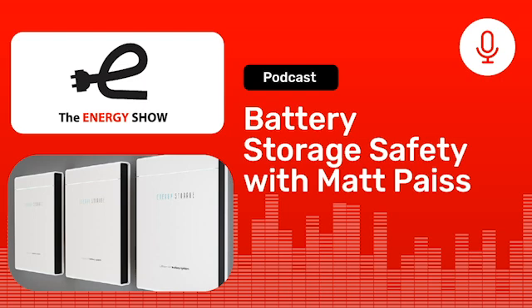The first thing they should look for is to see that it is UL listed, and that listing is 9540. So that's the first thing, to really ensure it is listed. There are some challenges with lesser-known batteries—you want to ensure it's a valid listing, as there are always counterfeit issues. But that's more difficult for a homeowner to evaluate. Still, that's the first thing: the listing.